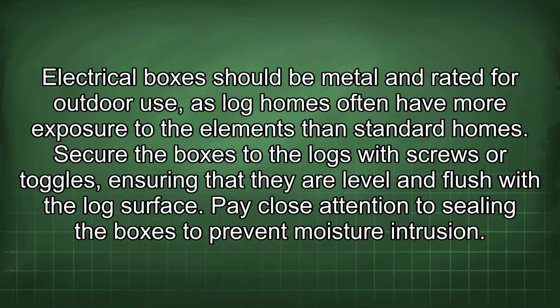Electrical boxes should be metal and rated for outdoor use, as log homes often have more exposure to the elements than standard homes. Secure the boxes to the logs with screws or toggles, ensuring that they are level and flush with the log surface. Pay close attention to sealing the boxes to prevent moisture intrusion.